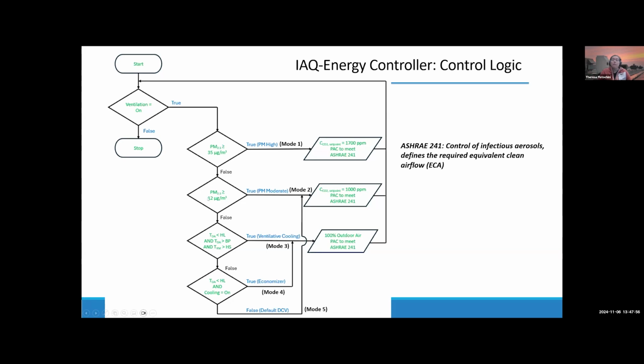If we're below 35, we check to see if we're above 12. That's the moderate air quality rating by the EPA. At least it used to be. Anyway, that's a long story. If it does that, we're going to just stay at 1,000 parts per million, which is a standard CO2 level, but we're not going to allow an economizer or anything like that to run. If we're below 12, we now enable the possibility to do ventilative cooling. We enable an economizer. If our outdoor temperatures are not in range for an economizer or ventilative cooling, we just run in a default mode and stay at 1,000 parts per million and kind of operate like business as usual.